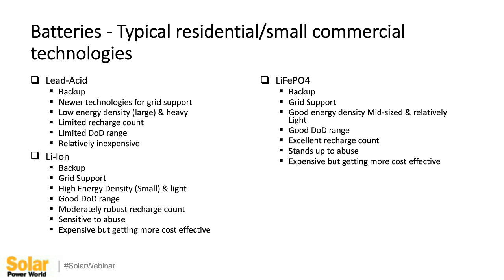Typically, lead-acid batteries have a limited recharge count, meaning how many times can you drain it and charge it back up before it doesn't want to be drained and charged back up anymore, and you start losing capacity. As for depth of discharge, lead-acid batteries typically don't like to go much further than about 50%, and most battery management systems will limit you by default to 50% depth of discharge.